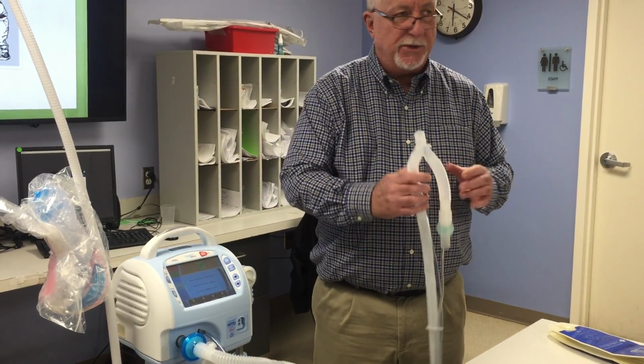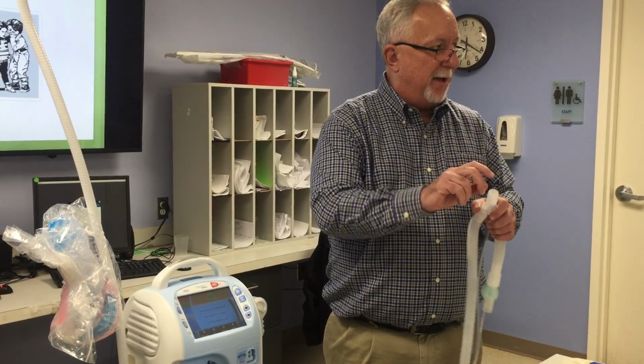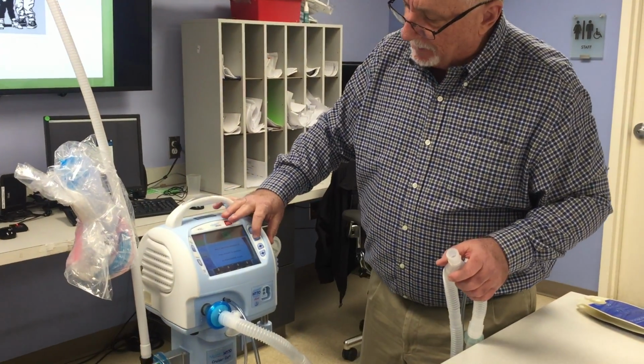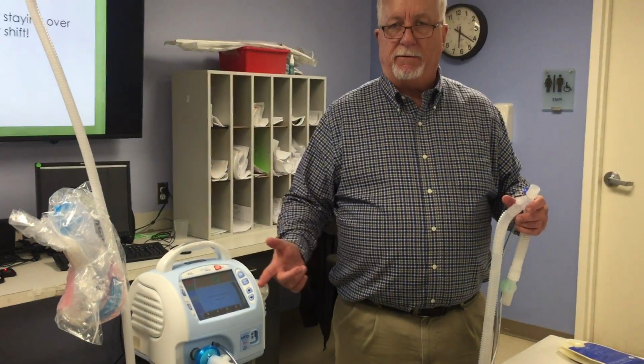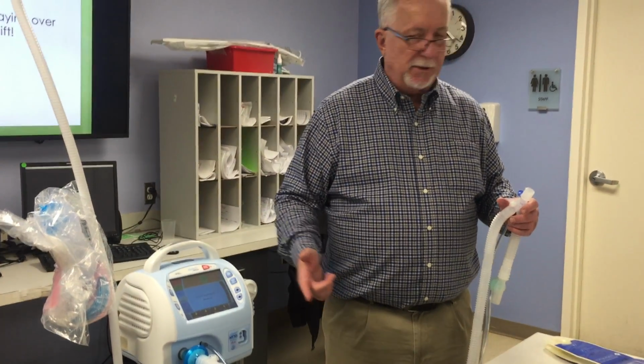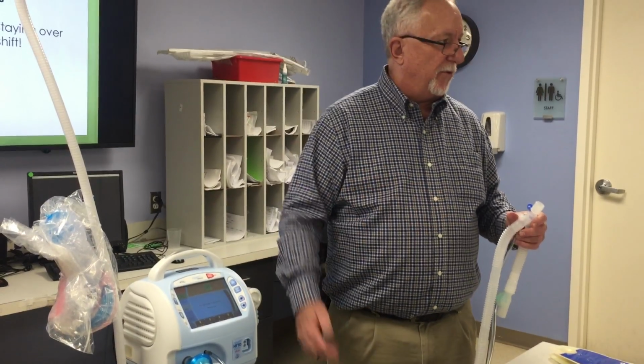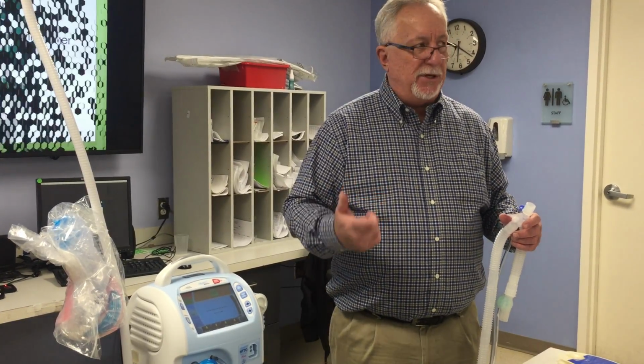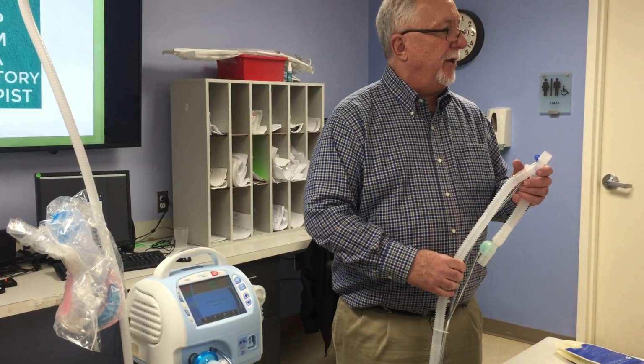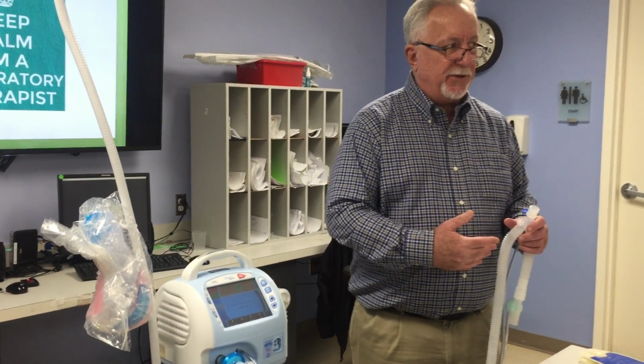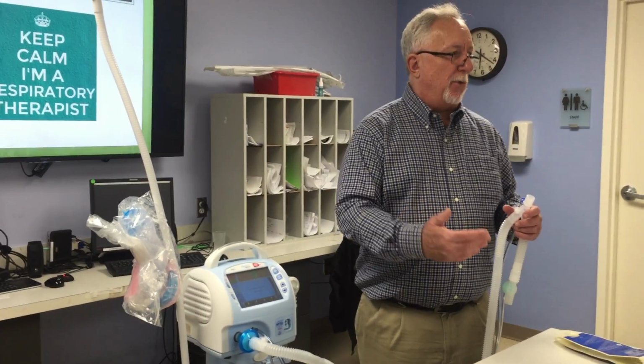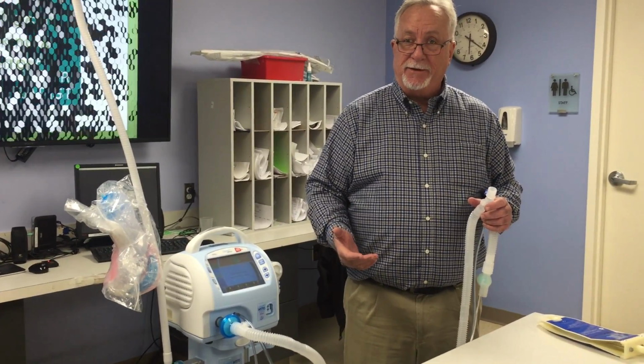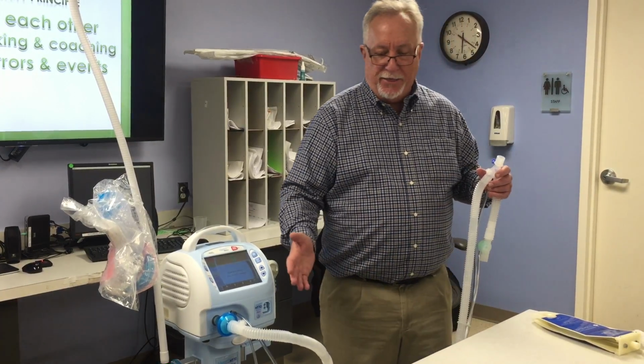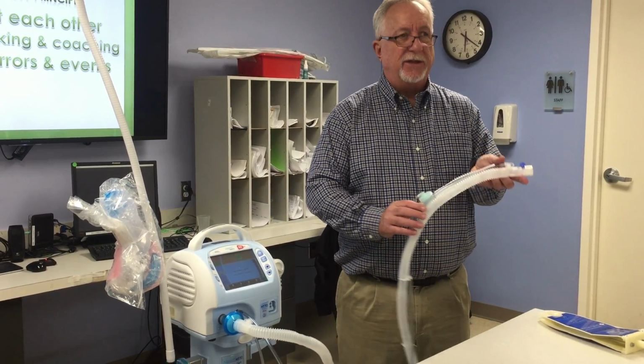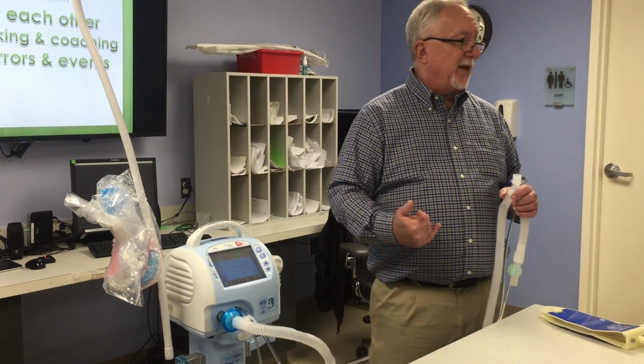So now what I'm going to do is open the circuit. If I had the little elbow on here with a cap, I would take that off, and now I'm going to hit accept. And that's step 2. And what you'll hear, I don't know if you can hear it, is it starting to ramp up the flow. And again, you only have to do this when you're putting a new circuit on it. Do you have to do that each time you put a new circuit on there? I would recommend it, that's our manufacturer's recommendation. What it does is make sure that your circuit doesn't have any gross leaks, the exhalation valve is working correctly, those types of things.